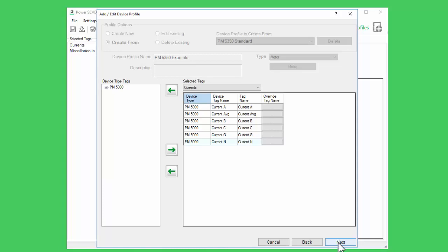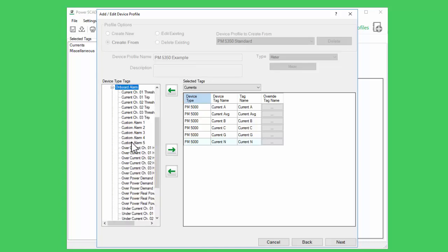The big difference this makes in Profile Editor is there are no checkboxes to create onboard alarms. Rather, there are specially configured variable tags in a group called onboard alarm that are designed to read values from an event log and write them to the alarm server. We'll discuss these variable tags in more detail as we cover the different drivers.